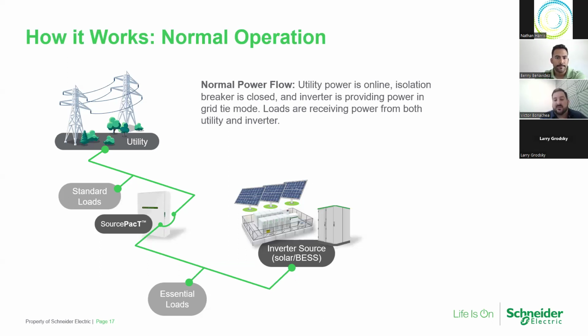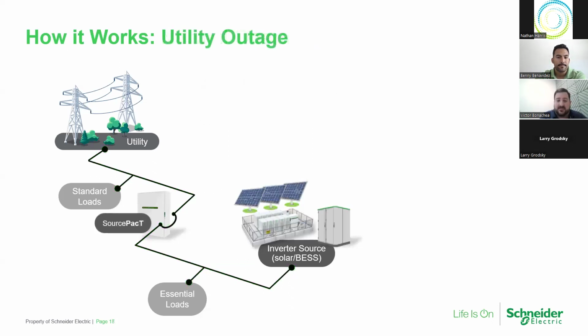And that allows your inverter system to charge off of the utility if it wants to, if it's a BESS system and you're using utility power to charge it. Or if you're playing with the energy pricing through your tariffs or through solar, it allows you to feed power back up, feed the loads on that emergency sub panel, or even push that power further upstream to the loads on your main panel, or even back to the utility if you have a back sell agreement with the utility. And that breaker is going to be closed most of the time because that inverter can be in grid tied mode.